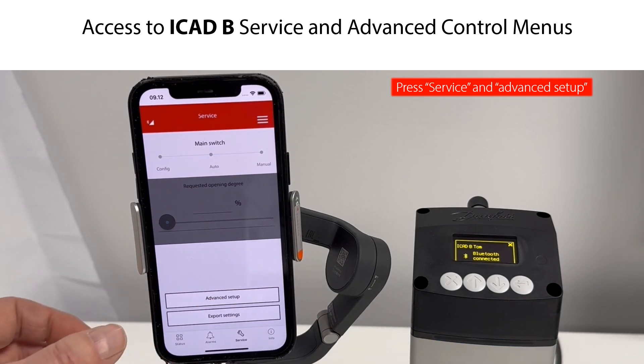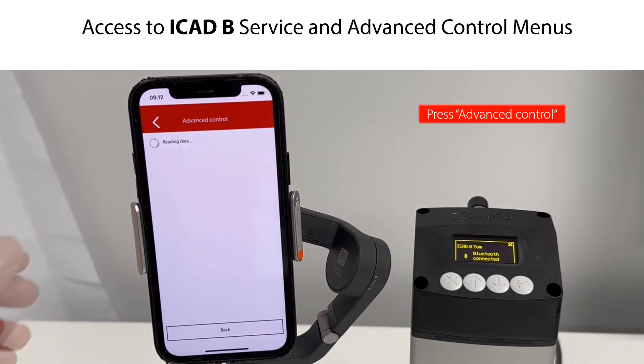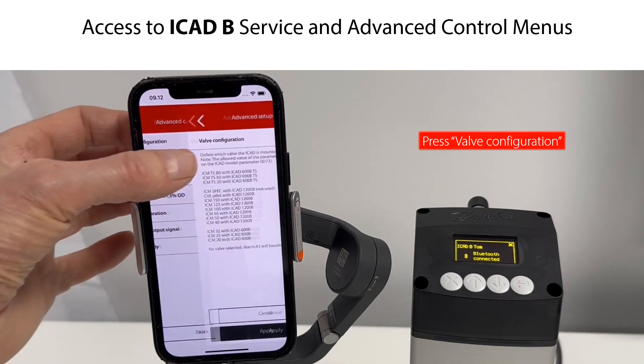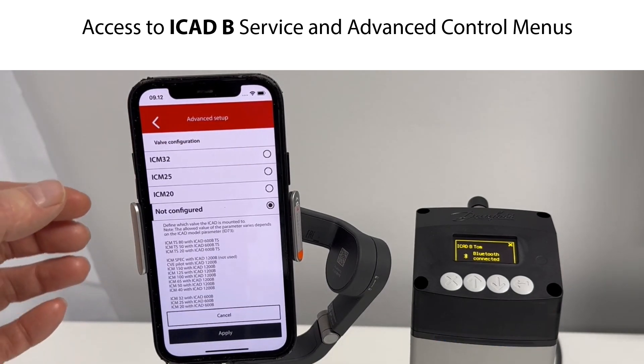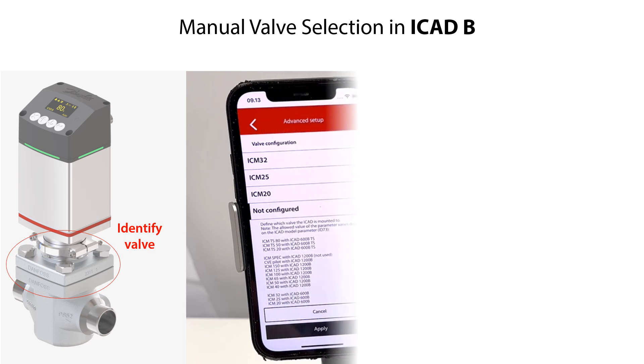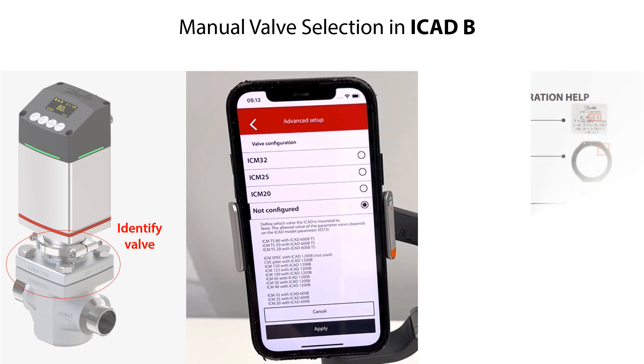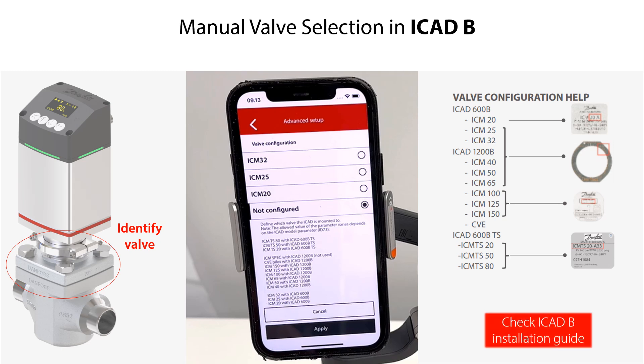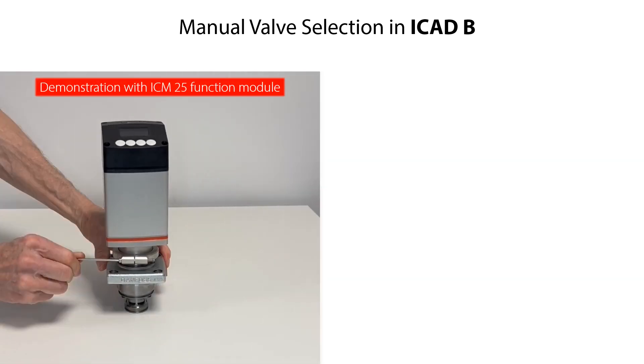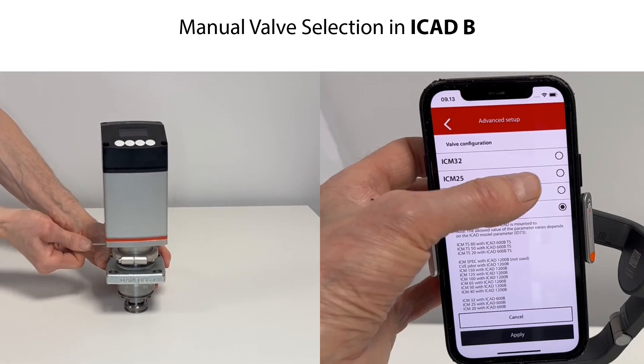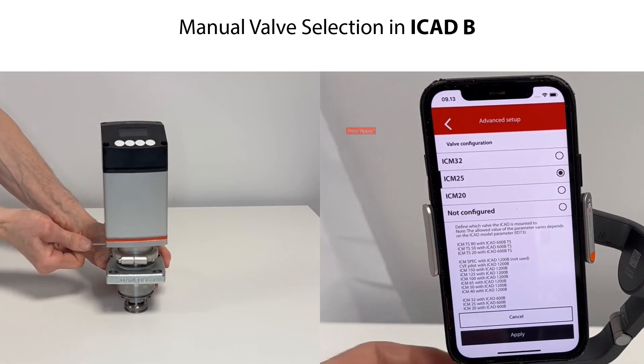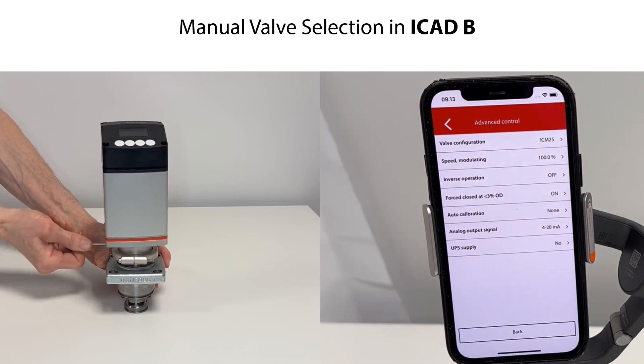To do a manual valve selection, press Service and press Advanced Setup, then press Advanced Control. Press Valve Configuration, which gives you an overview of valves suitable for the ICAD-B — currently the ICAD-B is specified as Not Configured. Select the valve type and size corresponding to the valve on which the ICAD-B is mounted. Since we are demonstrating with an ICM-25 valve function module, we select the ICM-25 valve and press Apply to confirm. The ICAD-B detects and configures the given valve, identified by a humming noise.